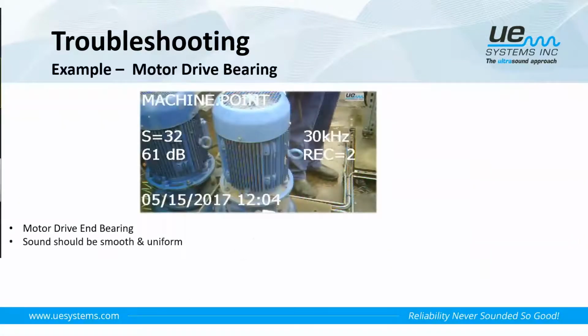So the first one was a motor drive end bearing inspected, driving a pump. Now, as a troubleshooting approach, we understand we expect to hear a smooth, uniform sound. So what we can do is take a reading, take a sound recording, and make a judgment. So this bearing here, this motor here, you can see from the image, the decibel value was 61 decibels, our frequency was 30 kilohertz, and we took the sound recording. And this is what it sounded like.